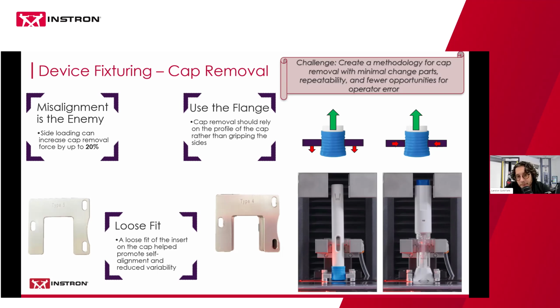Applying that side loading to the cap, even though it is rigid plastic, can still deform it somewhat, especially because you have a relatively soft, compliant, rigid needle shield inside of there. And any sort of side clamping on that could affect the cap removal force. So we wanted to make sure we designed it to always hold on to the curvature, the flange of the cap, as opposed to gripping it directly.